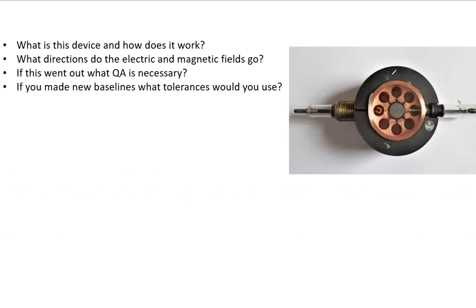If you had to make new baselines, what tolerances would you use? So we have a magnetron here, and it supplies microwaves for low-energy LINACs, typically 12 MV or less. It's less costly but also less stable than a klystron.